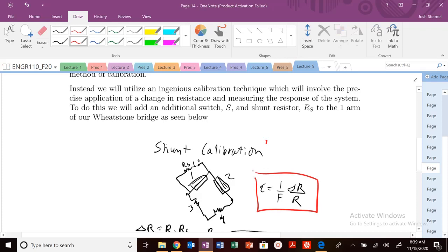So one way we know we have this relationship where strain is going to change as we change the resistance. So one way you can calibrate a strain gauge is imagine we have this Wheatstone bridge configuration, standard configuration as usual. But we could see in this arm here that we have a strain gauge, this shunt resistor here, RS, and then there's a switch here.